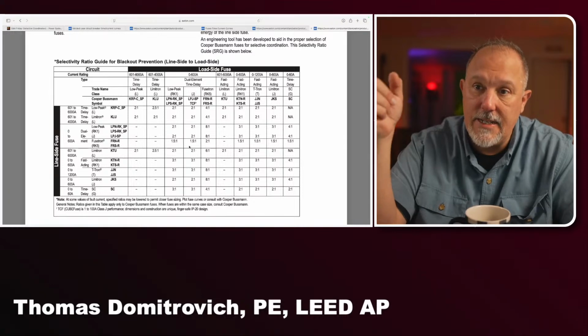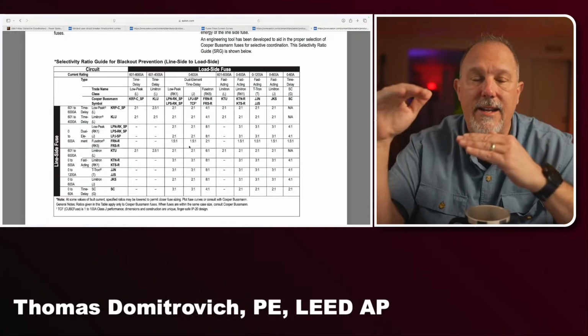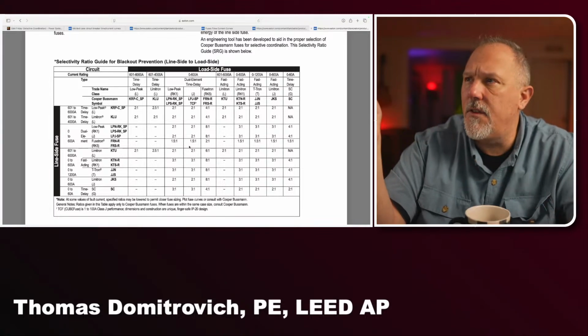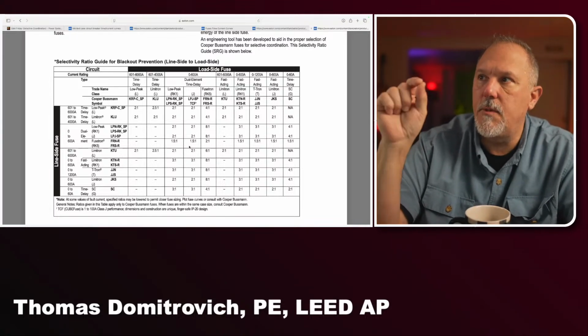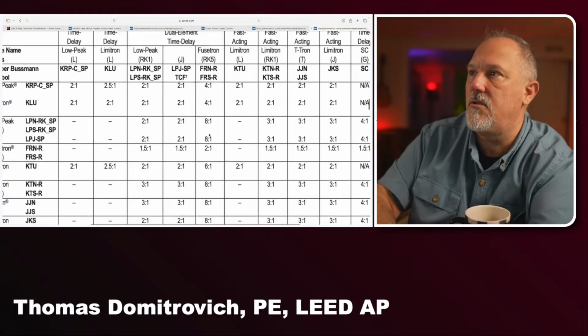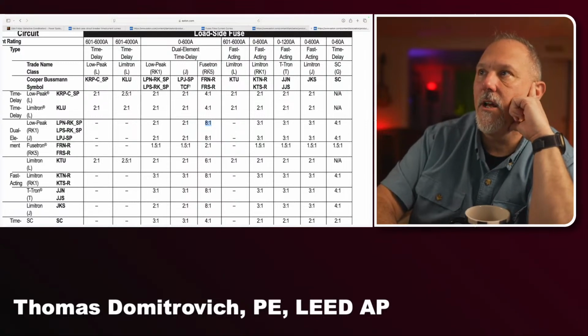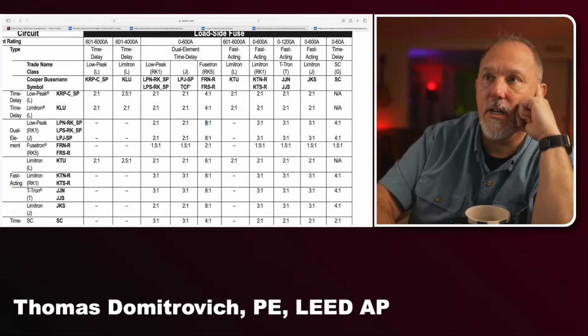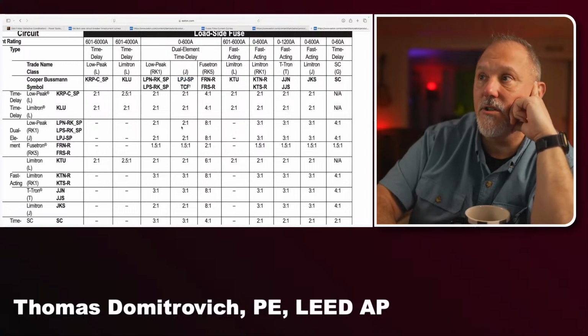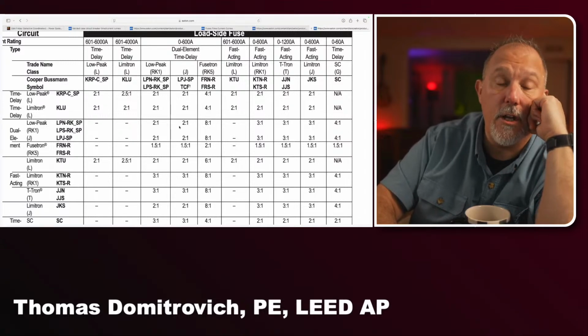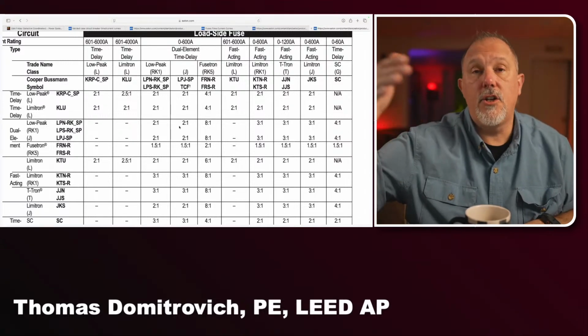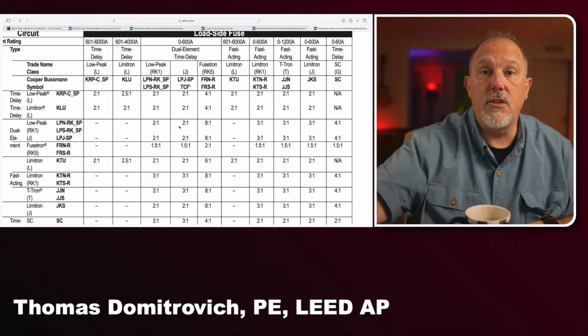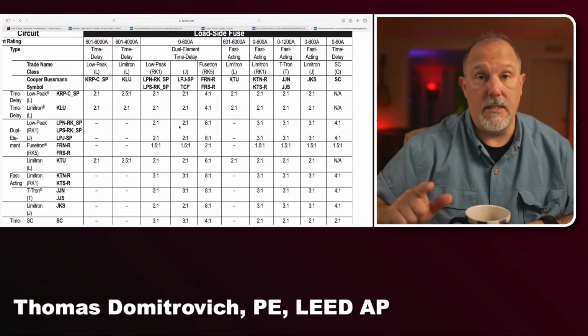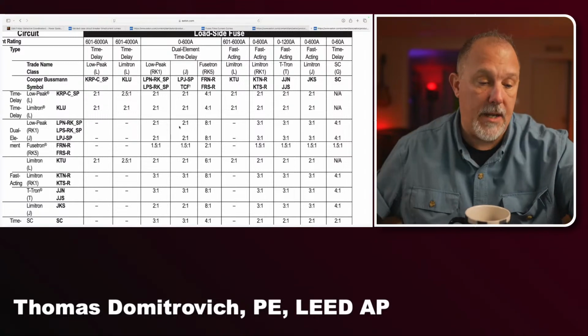And what they identify here is that when you have a load side and line side fuse, for the most part a lot of these are 2-to-1 ratios, but you'll see some 8-to-1 ratios in here. If I zoom in, there's an 8-to-1. So if I have a load side RK5 downstream of a Low-Peak RK1, it's an 8-to-1 ratio. But if I have an LPJ or a TCF downstream of that Low-Peak, it's a 2-to-1 ratio. So the fuse people try to drive that current limiting nature and just say, look, maintain a 2-to-1 ratio and you're done. And here's the nice thing about that.